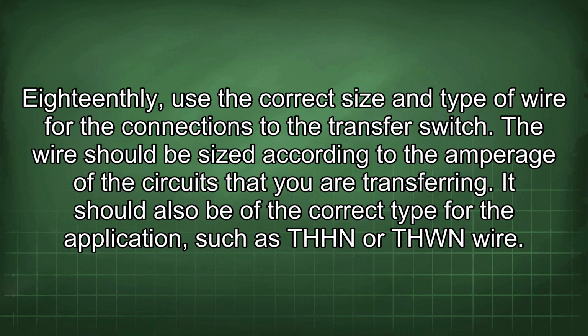18thly, use the correct size and type of wire for the connections to the transfer switch. The wire should be sized according to the amperage of the circuits that you are transferring. It should also be of the correct type for the application, such as THHN or THWN wire.